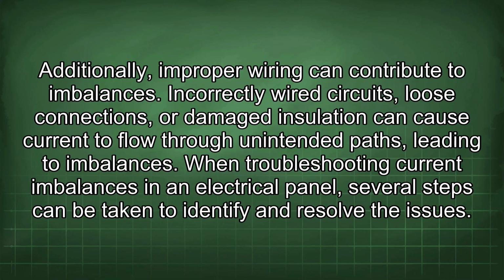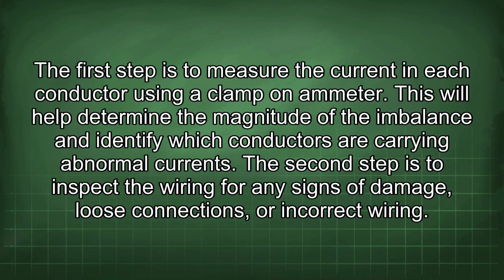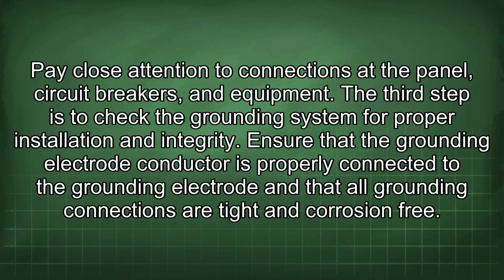When troubleshooting current imbalances in an electrical panel, several steps can be taken to identify and resolve the issues. The first step is to measure the current in each conductor using a clamp-on ammeter. This will help determine the magnitude of the imbalance and identify which conductors are carrying abnormal currents. The second step is to inspect the wiring for any signs of damage, loose connections, or incorrect wiring. Pay close attention to connections at the panel, circuit breakers, and equipment.